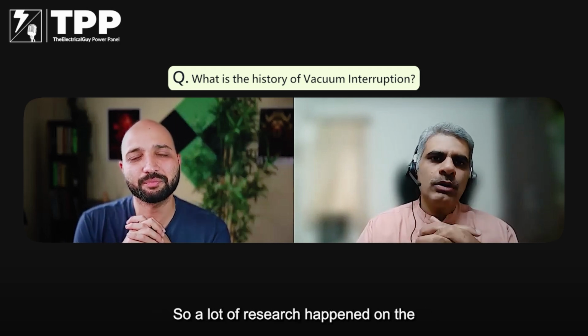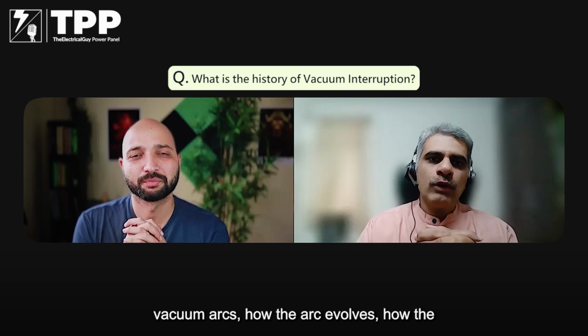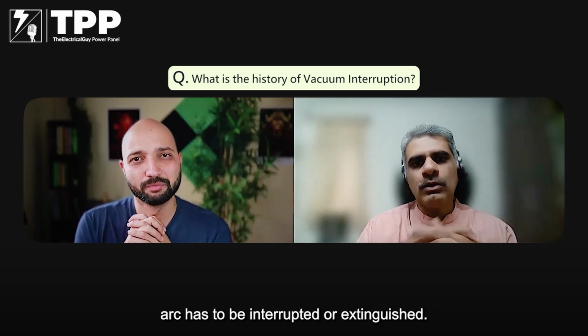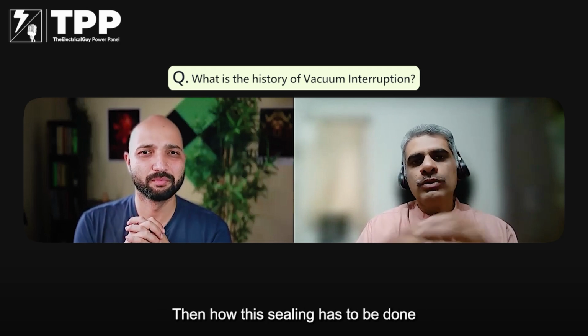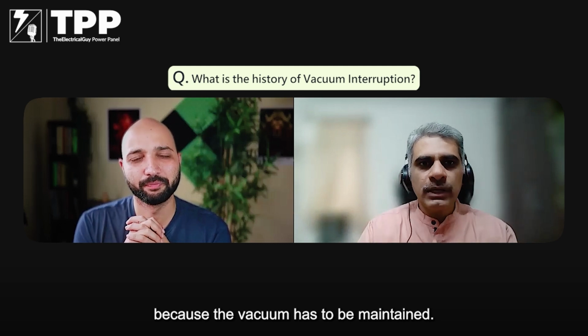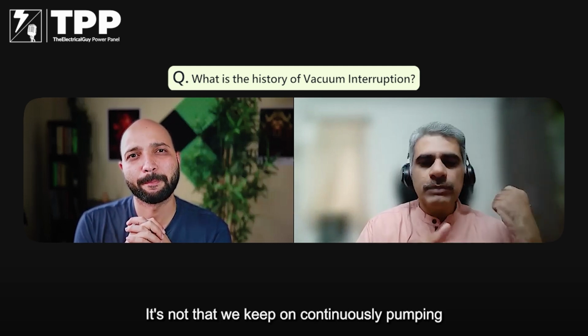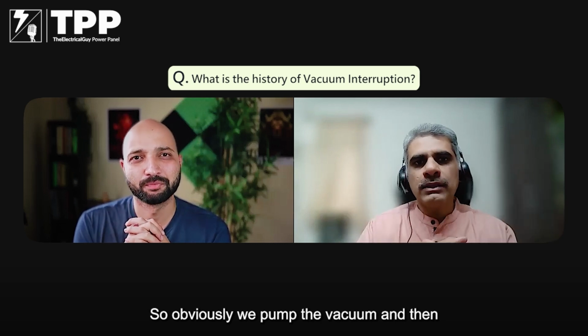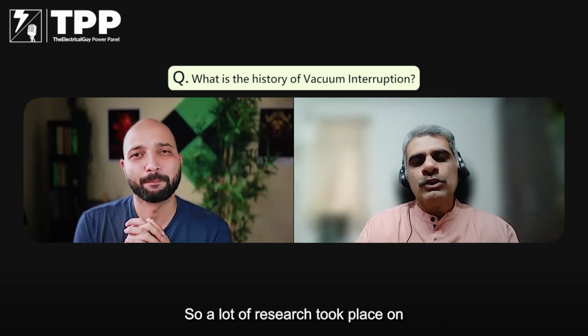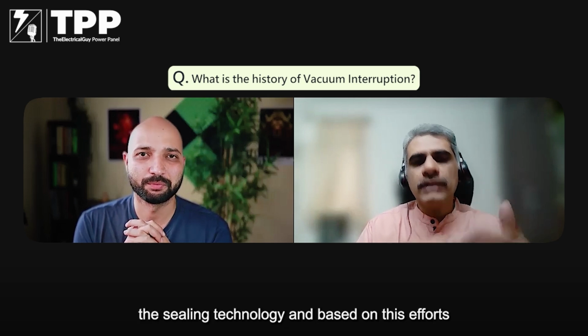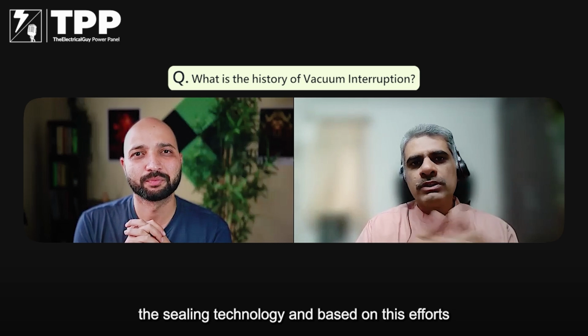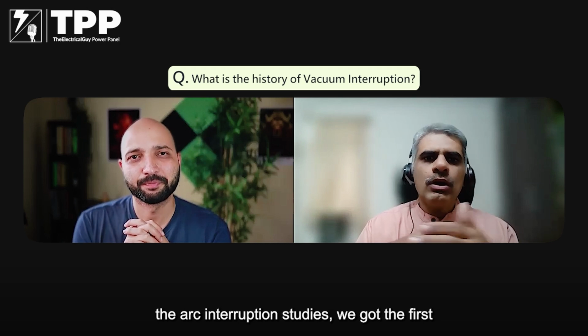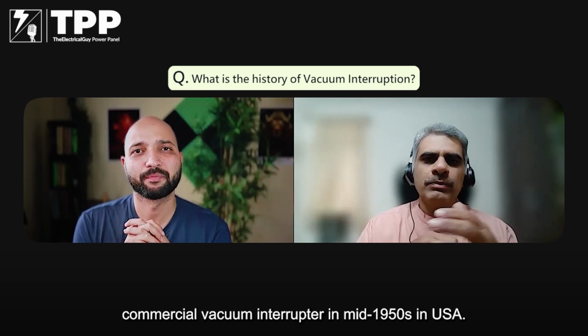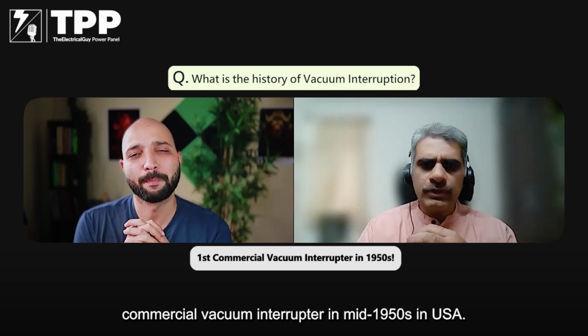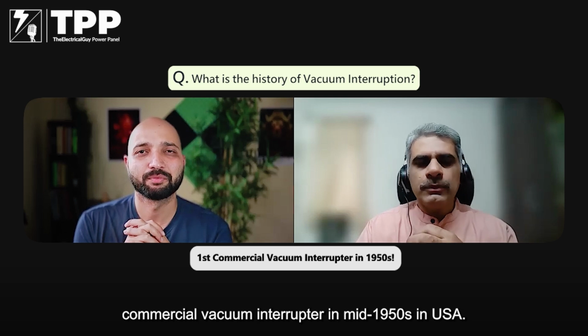So a lot of research happened on vacuum arcs, how the arc evolves, how the arc has to be interrupted or extinguished. Then how the sealing has to be done, because the vacuum has to be maintained. It's not that we keep on continuously pumping the vacuum. So obviously we pump the vacuum and then it should be a sealed for life kind of device. So a lot of research took place on sealing technology. And based on these efforts in sealing technology and also the arc interruption studies, we got the first commercial vacuum interrupter in the mid 1950s, in USA in those times.